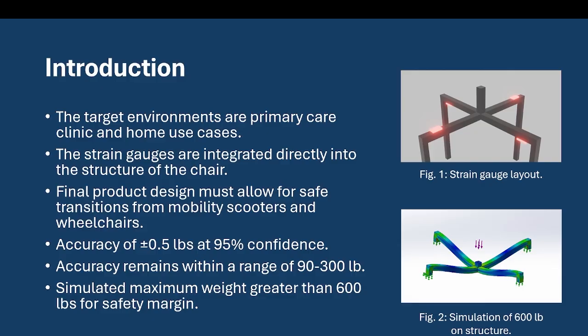In use, a mobility impaired individual will shift from a wheelchair or scooter onto the sitting scale chair. This may require the assistance of another person in some cases, but will be similar to getting in and out of a regular wheelchair. To ensure that the system is as accurate as a standard bathroom scale, an accuracy of plus or minus 0.5 pounds at 95% confidence is required. This accuracy must be true within a range of 90 to 300 pounds. To ensure a wide safety margin, the CAD model was simulated under 600 pounds without failure.